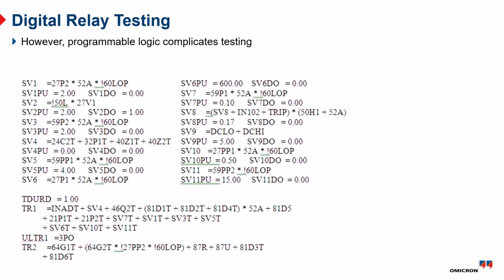In SEL logic, the plus is an OR, and the multiply symbol is an AND. So here you can see a SEL logic variable equation where you have an undervoltage element ANDed with a breaker position and also ANDed with a NOT loss of potential. So in order to operate this SV6, and you'll see SV6 in the trip equation, you go to SV6, this is what's in SV6. In order for SV6 to assert, you have to be below the pickup of the 27, the breaker has to be closed, and you cannot have a loss of potential situation. Then SV6 asserts, TR1 asserts, and whatever output's programmed to assert when TR1 asserts, the relay trips. So quickly, for those of you that don't know, this is how SEL logic works.